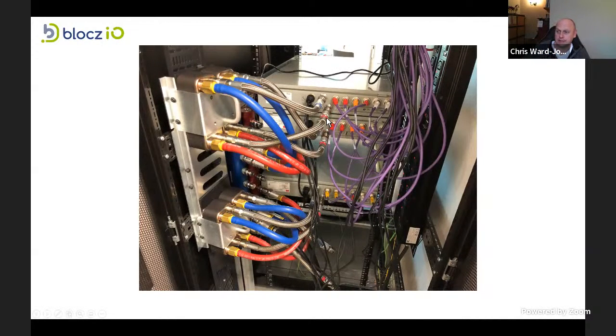What you can see here is the hot coolant, the hot dielectric fluid, taken out of the chassis through a heat exchanger and then pumped back into the chassis. So you've got a sealed loop here, effectively, of dielectric fluid. The dielectric fluid in here never leaves. It just cycles around its heat exchanger.